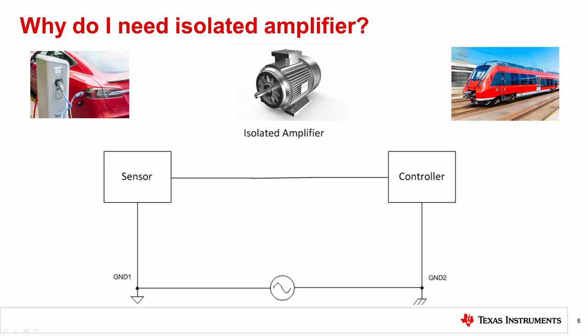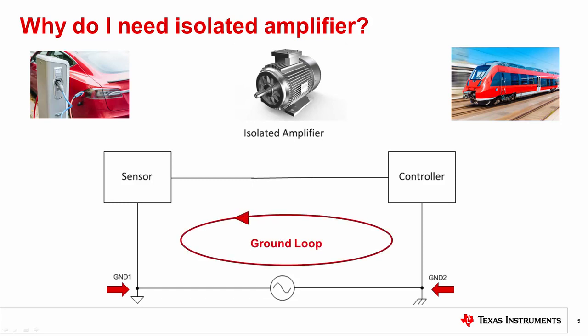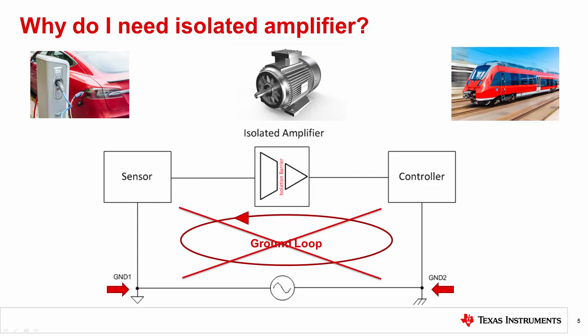Isolated amplifiers are widely used in many industrial and automotive applications, but why are they needed? One common reason for using an isolated amplifier is to break ground loops. Electrical installations can cause large ground potential differences between two remote nodes, ground one and ground two. A direct connection between these two grounds closes the ground loop. Equipment like electric motors can inject large noise currents into the ground, thus creating a ground loop current that can appear in the signal path. Isolated amplifiers remove the signal path noise from the ground loop and protect the system from ground loop potential difference.